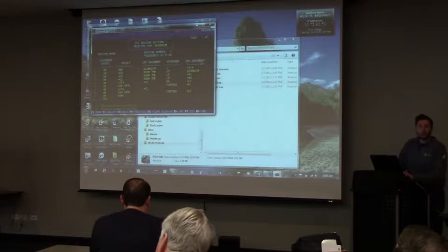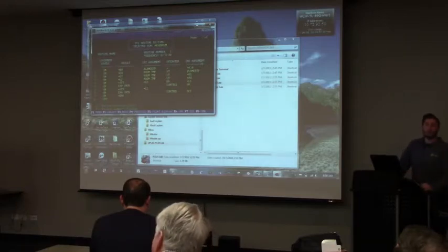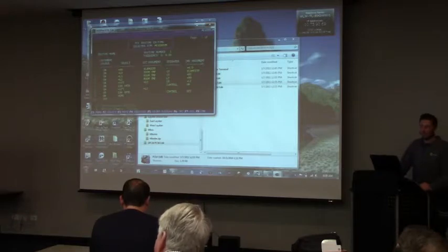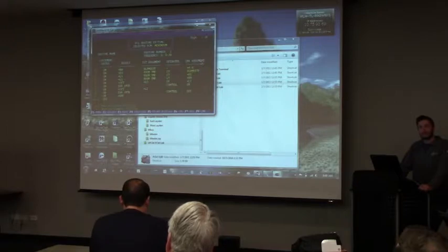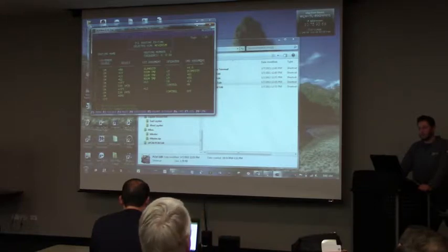And this is a good example of how not to write the program. Because they have one set of logic turning something on and another set of logic turning it off. Whenever you do that, you have the possibility that you forgot something. So it's always a good idea to write half of it. Write whatever turns it on, and then put an else statement and turn it off.